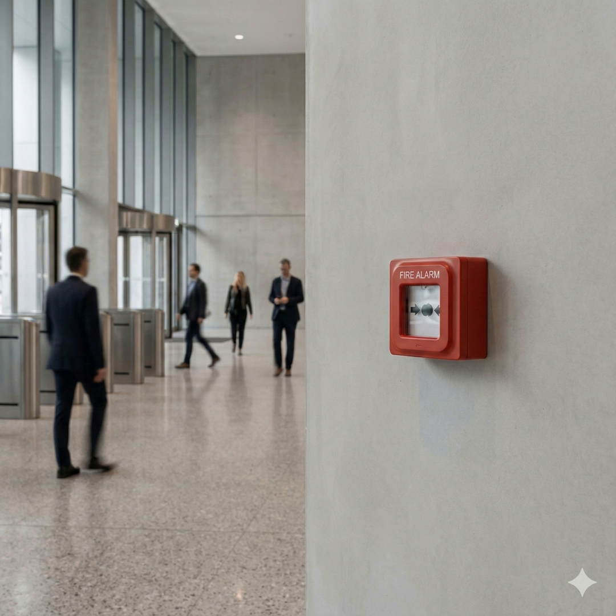And finally, acceptance testing, which is governed by NFPA 72, Chapter 14. This is the big one. It's a full demonstration of the system's performance to the authorities and the owners. It confirms everything works as programmed before the building can be legally occupied. Once it's installed and certified, the challenge shifts to the long-term operational life cycle.